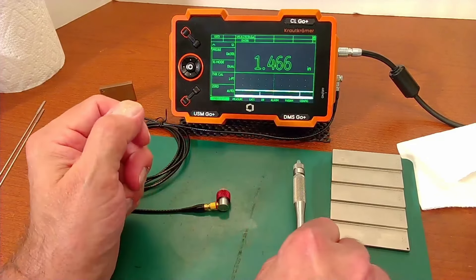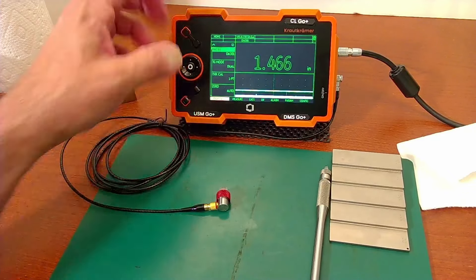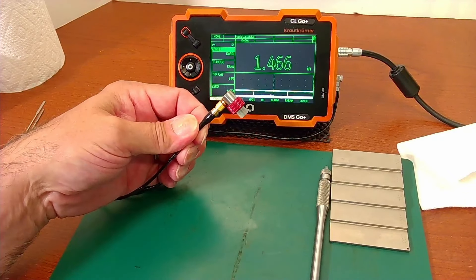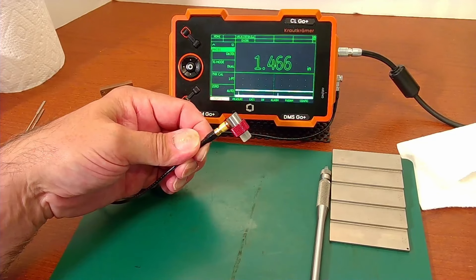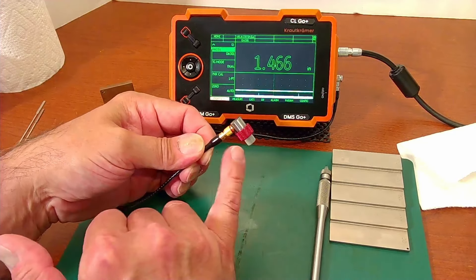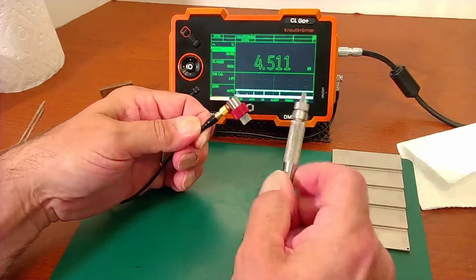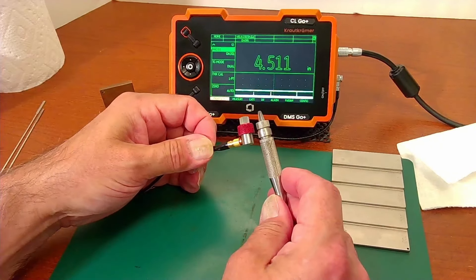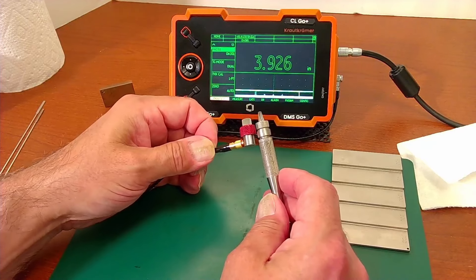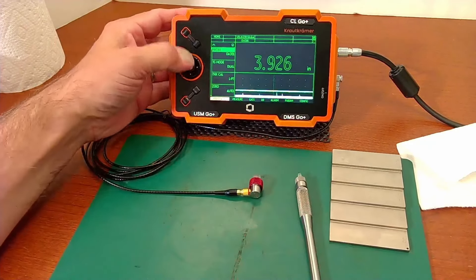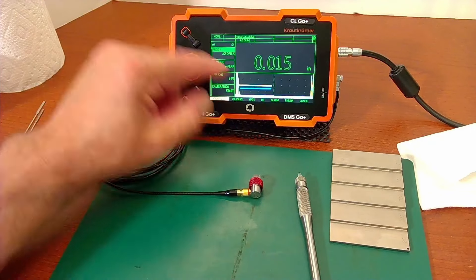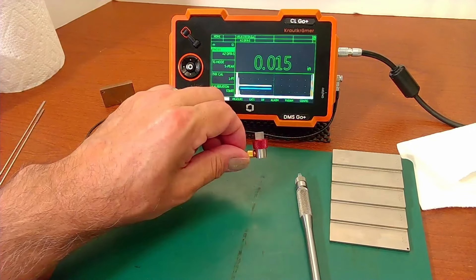The first thing we're going to do is pick a probe that is close in design. One of my favorite probes for thinner materials on the DMS Go is the Alpha 2 DFR, our classic delay tip probe. This is close conceptually to the K-Pen. So let's go ahead and select the Alpha 2 DFR short, the shorter delay tip, as a starting point.